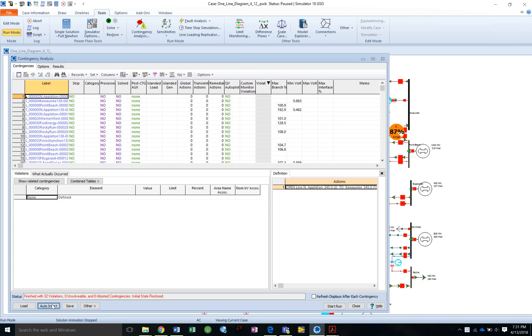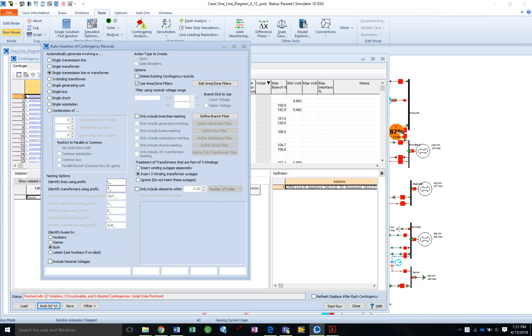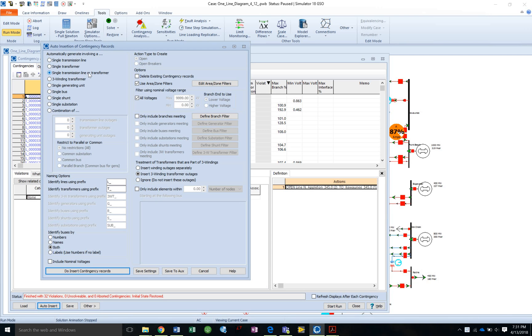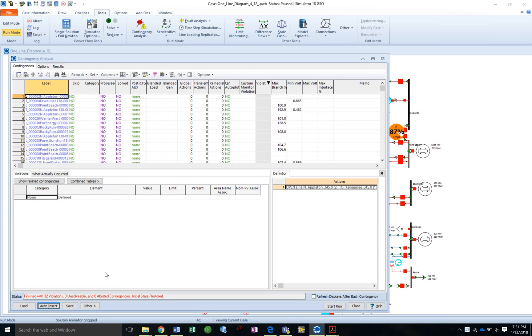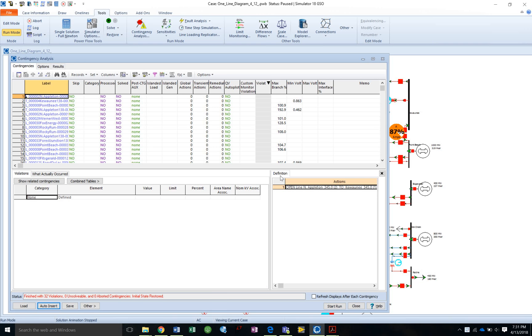So we go to auto-insert. Then we want single transmission line or transformer. All the settings look good. We'll do insert contingency records. So now everything's inserted.